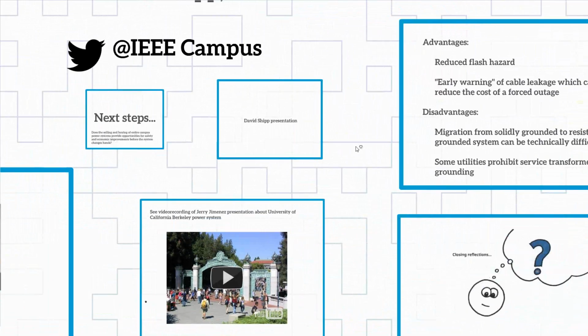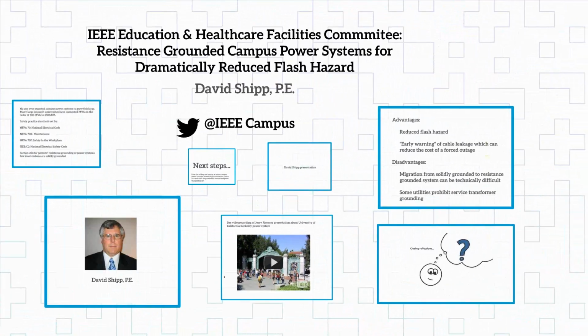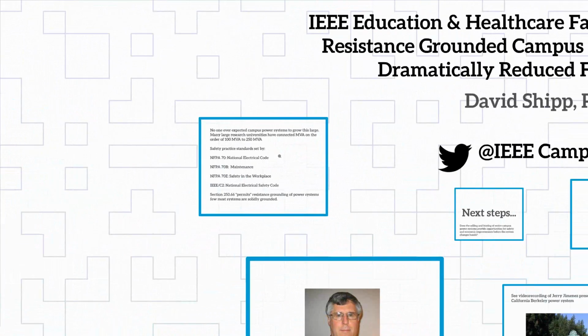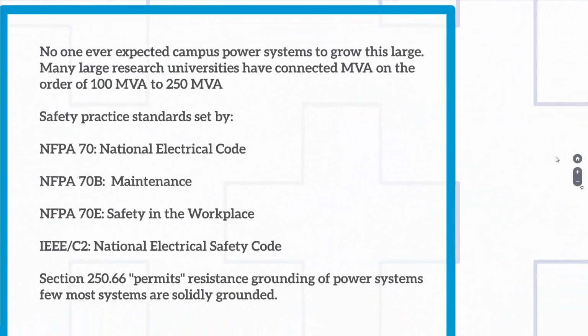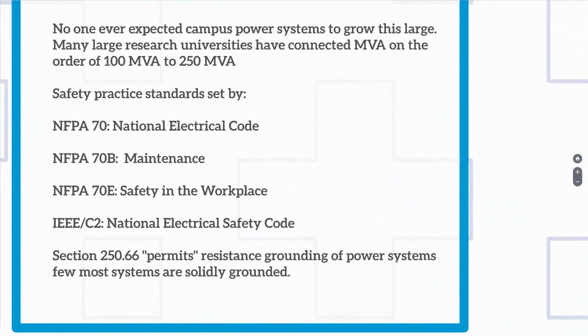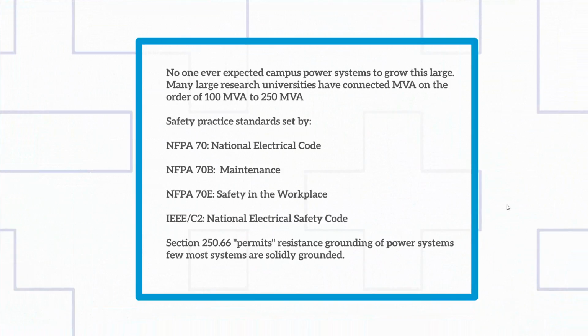If I go to retrofit, I do 100-to-5 split core, so a CT around the cable, so I don't have to take 30 sets of 15 kV terminations and spend 6 months and $100,000 taking the terminations loose, moving 30-year-old cables, slipping CTs over them, and putting them back on. So there's a lot of different ways to cover that, and the new digital relays help immensely to work around that. And then there's all kinds of diagnostics that you can get into for leakages and so on. So the problem is it's a case of too much information almost. Mm-hmm. Jim Harvey's people would be on overload if they put them everywhere. But the point is there's ways to work around that today that we did not have 20 years ago.